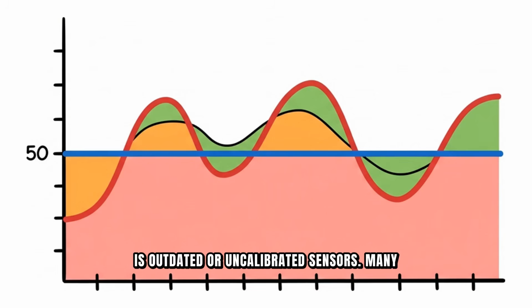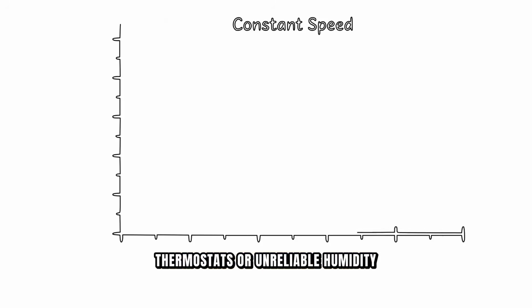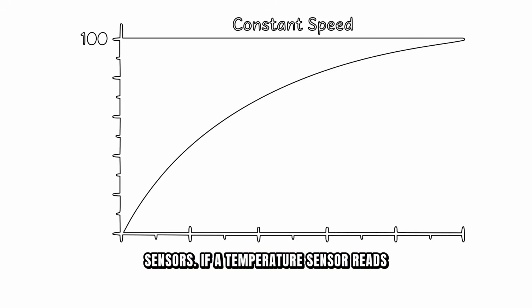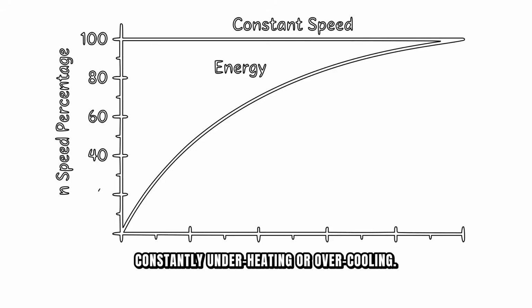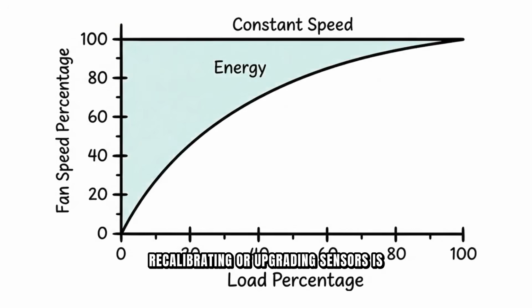Sixth is outdated or uncalibrated sensors. Many older AHUs still have mechanical thermostats or unreliable humidity sensors. If a temperature sensor reads 5 degrees high, your system is constantly underheating or overcooling. Recalibrating or upgrading sensors is often one of the highest ROI investments in building efficiency.